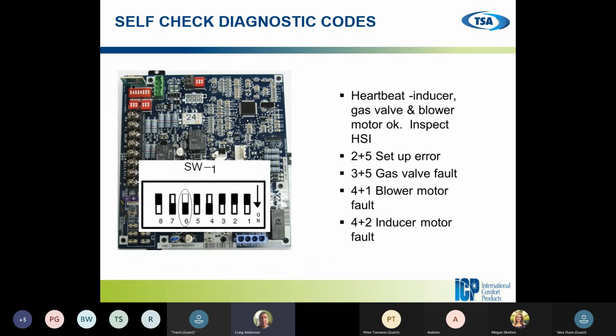So once you're done the test and you figure out what the problem is, or you've gone back to a heartbeat, you're going to have to flick that dip switch 6 back to the normal position, or it's going to go into an error code when you actually start hooking everything back up again. So always remember to put it back to the proper position.